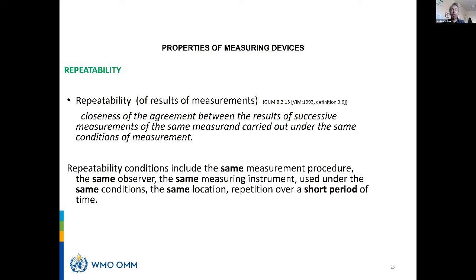It doesn't have much weight or meaning in that case, but repeatability still exists - you can try to measure it. For example, take a low-level instrument, make measurements, repeat them, and you might get a repeatability of 0. With more resolution, you'll start to see a little repeatability - it means you have noise, statistical aspects, time passing, and some environmental conditions may have changed without you detecting it. You have limits.